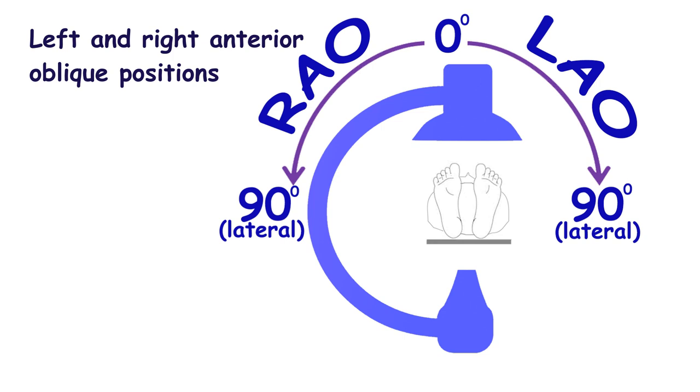If the image intensifier is rotated to the right side of the patient, this position is called right anterior oblique, or RAO. If the image intensifier is rotated 90 degrees in either direction, the position is called lateral.